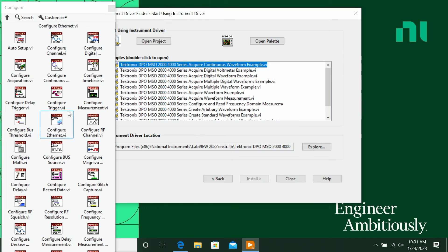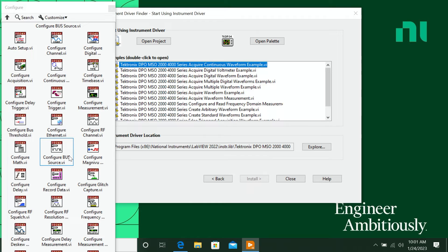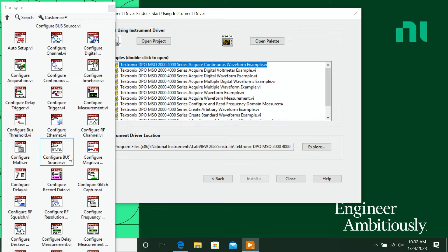tons of functions for configuring. Basically what we've done is we've gone in and wrapped all the SCPI commands that you need to send to control this instrument. So rather than having to go into the manual and see exactly what you need to send, you can just drag and drop one of these commands and it does it for you.